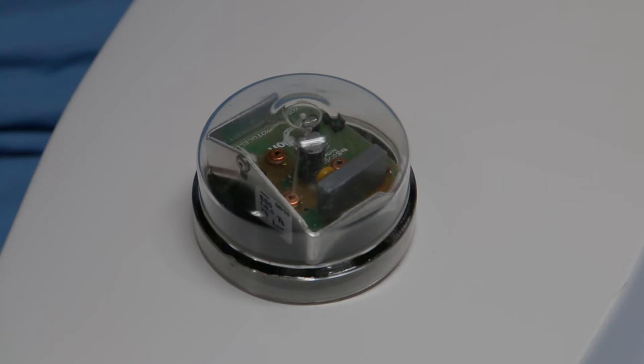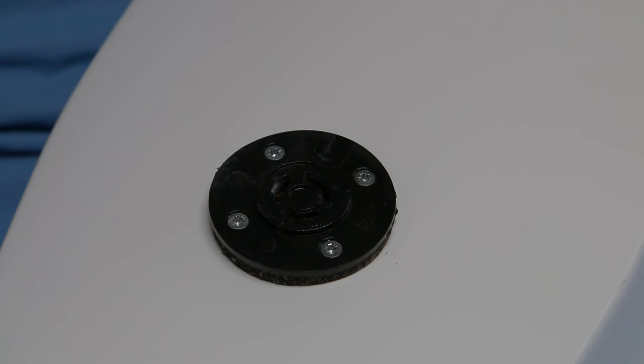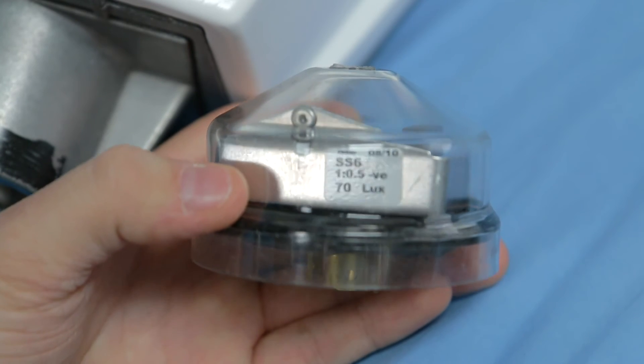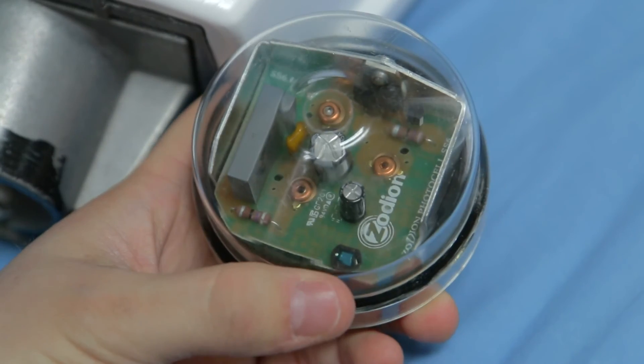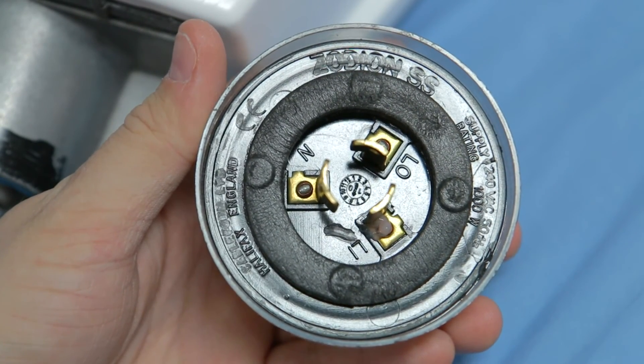Here's a quick look at the photocell control unit. This controls when the light goes on when it gets dark, and when it switches off when it gets light. It uses a standard NEMA socket. This particular photocell is a Zodion SS6, set to come on at 70 lux. There's the detector right where my thumb is. If we turn it over, you can see the live, the neutral, and the switch load.